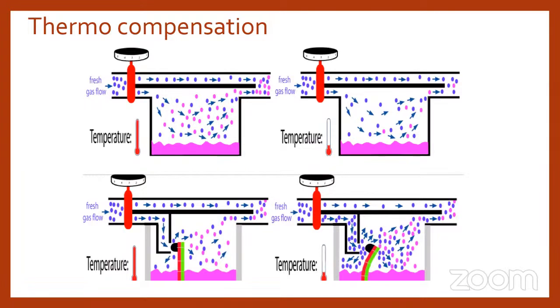So the volume of the fresh gas that enters the vaporizing chamber will be more. The more volume of air enters the chamber, the more vapor will be mixed with the air, and more concentration will be delivered at the patient end. So this is how thermocompensation works. Basically, when the temperature is high, the flow will be limited. When the temperature is low, the flow will be more. So the vapor conversion will be more, and ultimately the amount of anesthesia delivered to the patient will remain the same.